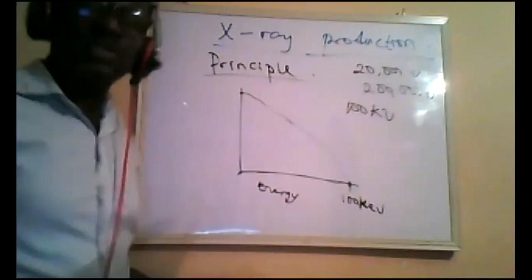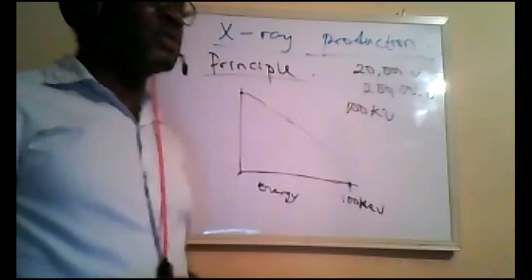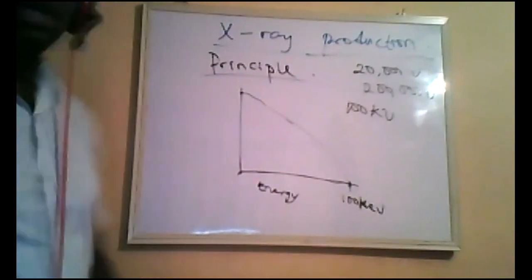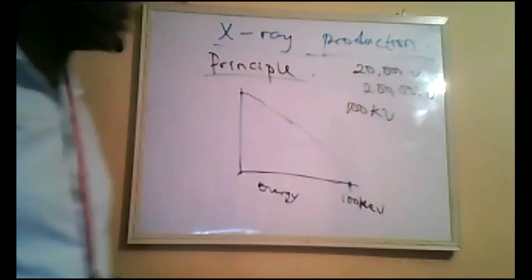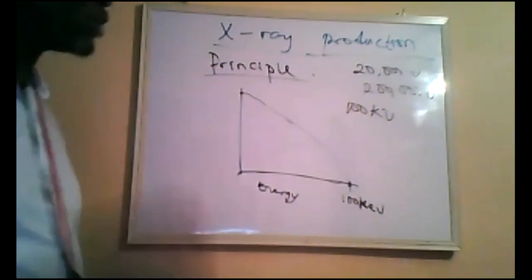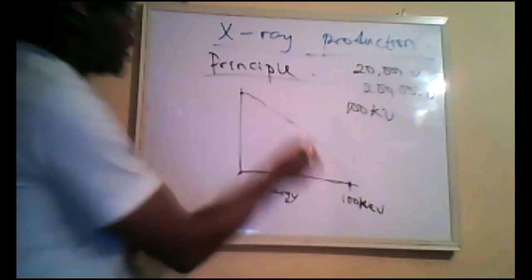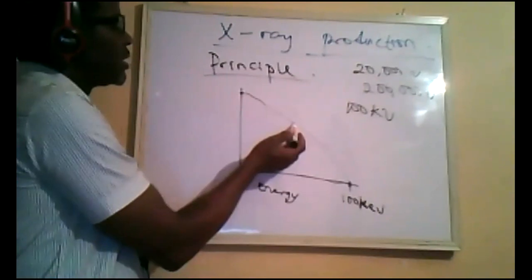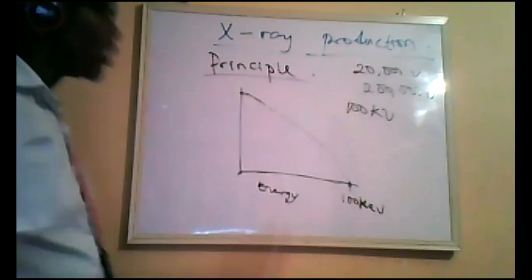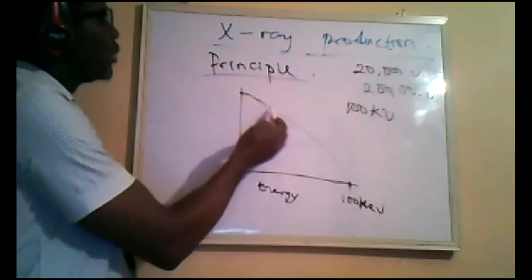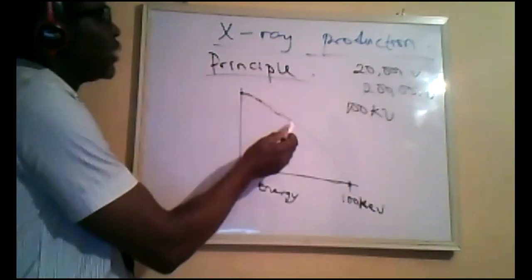But in X-rays, in all X-ray equipment, we normally introduce a filtration, and the filtration can come in form of both inherent and added filtration. I think we are going to get to that later. But essentially, what that does is to actually change the shape of this spectrum, because we have so many of these low energetic portion.